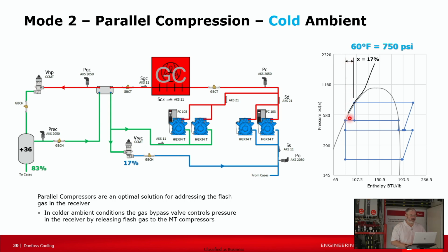So at 17% flash gas, we're just going to send that straight into the medium temp suction line. Even though we've got 17% of the refrigerant in the flash tank that doesn't go to the cases and do work, CO₂ is a much better refrigerant. You're still more efficient than HFC to handle that 17% right into the medium temp.